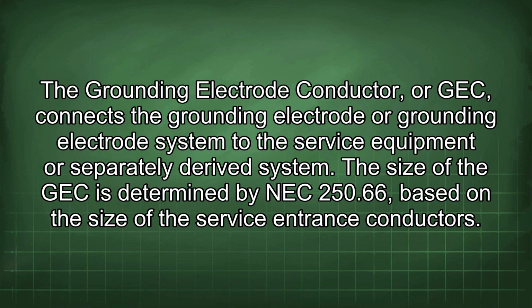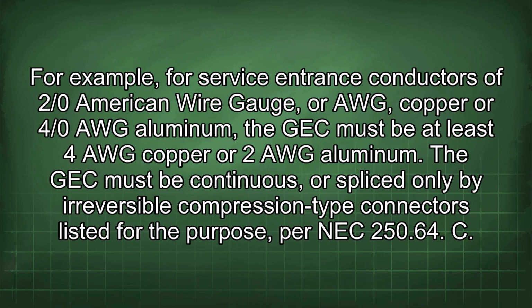The grounding electrode conductor, or GEC, connects the grounding electrode or grounding electrode system to the service equipment or separately derived system. The size of the GEC is determined by NEC 250.66 based on the size of the service entrance conductors. For example, for service entrance conductors of 2/0 American wire gauge, or AWG, copper or 4/0 AWG aluminum, the GEC must be at least 4 AWG copper or 2 AWG aluminum. The GEC must be continuous or spliced only by irreversible compression type connectors listed for the purpose per NEC 250.64 C.